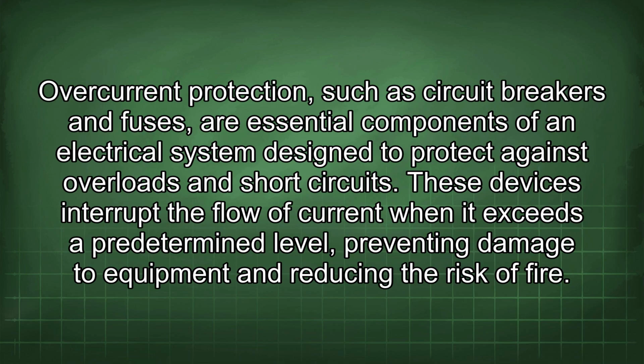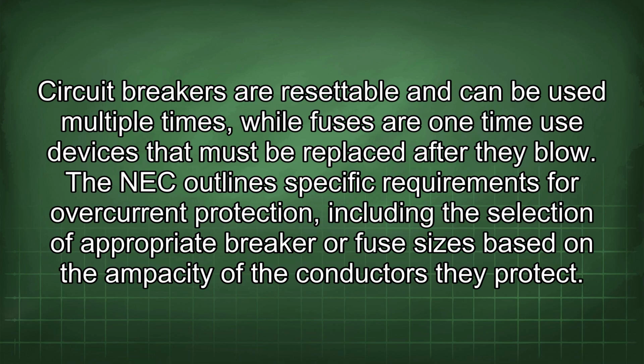Overcurrent protection, such as circuit breakers and fuses, are essential components of an electrical system designed to protect against overloads and short circuits. These devices interrupt the flow of current when it exceeds a predetermined level, preventing damage to equipment and reducing the risk of fire. Circuit breakers are resettable and can be used multiple times, while fuses are one-time use devices that must be replaced after they blow. The NEC outlines specific requirements for overcurrent protection, including the selection of appropriate breaker or fuse sizes based on the ampacity of the conductors they protect.